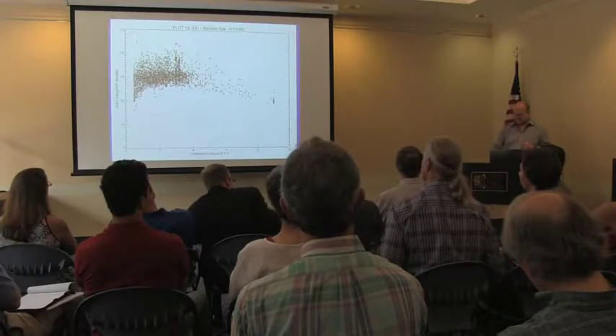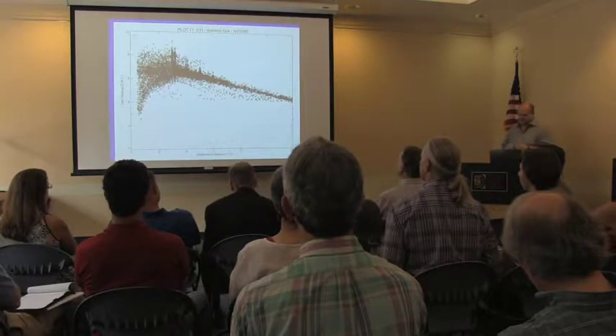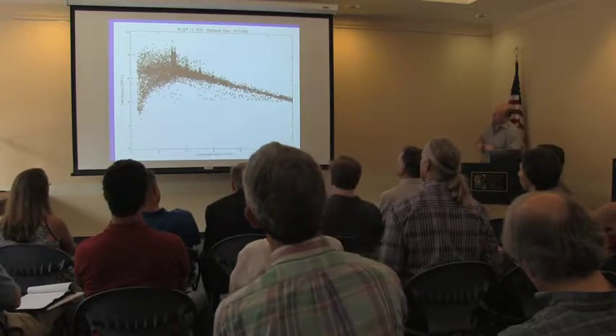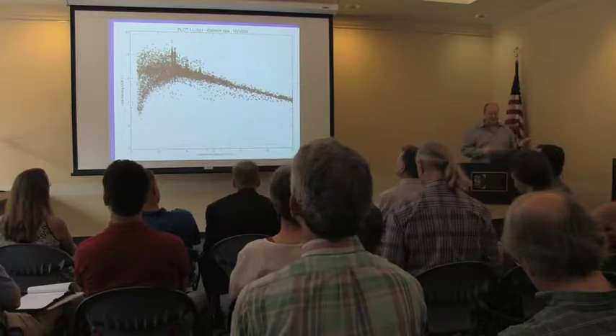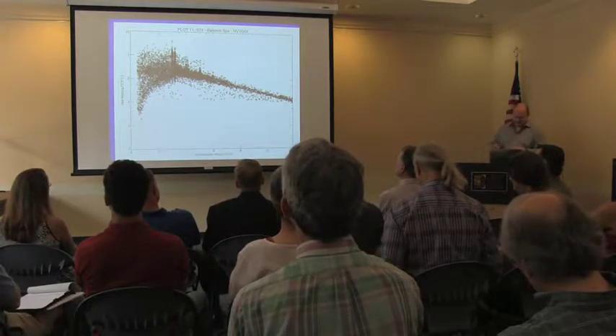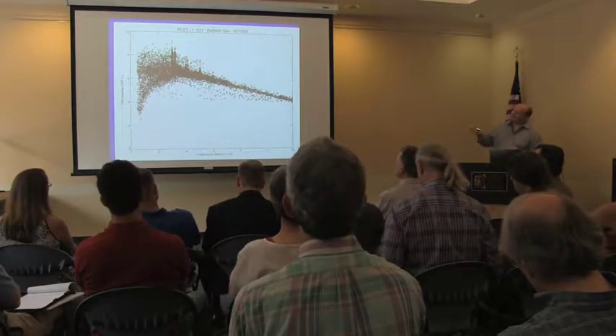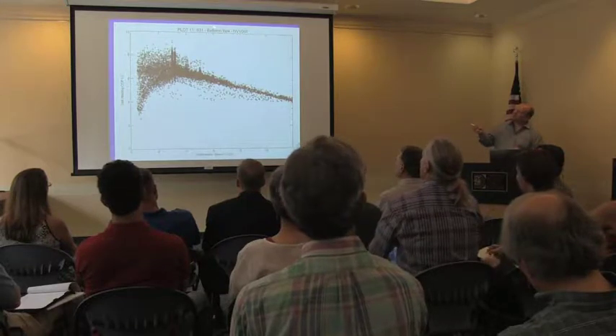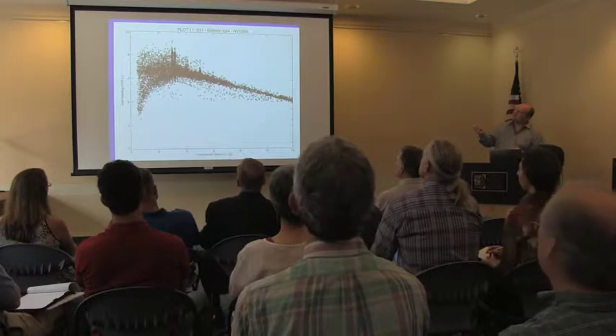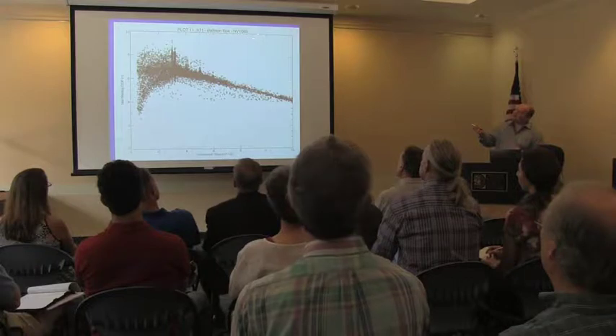the heat against. This is a COP, the coefficient of performance, how much energy goes in, how much energy goes out. You can see here the curve. These are ultra efficient units. These are variable speed units, the most modern ones we have. This is a 5-ton unit.